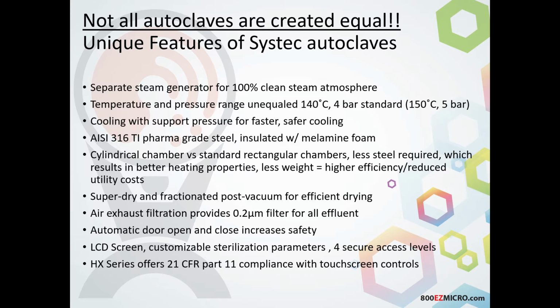We offer air exhaust filtration for all effluent, so if you are putting this in a pathogen laboratory where you will need to filter that air when we pull a pre-vacuum on the instrument, that is an option for us as well. And then everything before it goes down the drain will run through that exhaust filtration. We do offer automatic door open and closing, which increases safety. We'll go through that when we go to the practical portion.